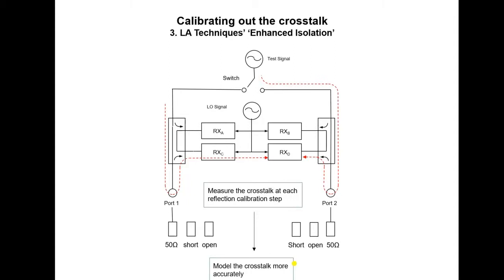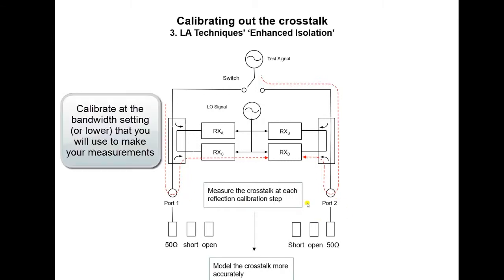Now, it is important to remember that for this technique to work well, as indeed any other crosstalk calibration technique, you need to make sure you make the calibration measurements at the bandwidth at which you will make your DUT measurements, or even lower. For example, if you wish to make measurements at 100Hz, then you should make your calibration measurements at 100Hz, or even 10Hz. The enhanced isolation calibration technique can work well, but the cost is that you need to make four slow calibration measurements.